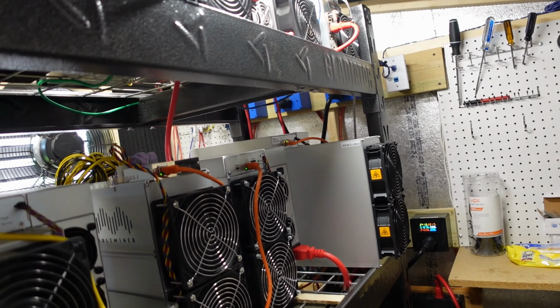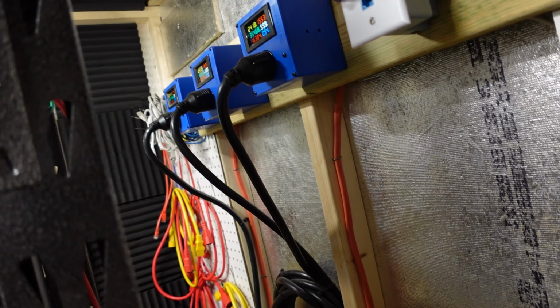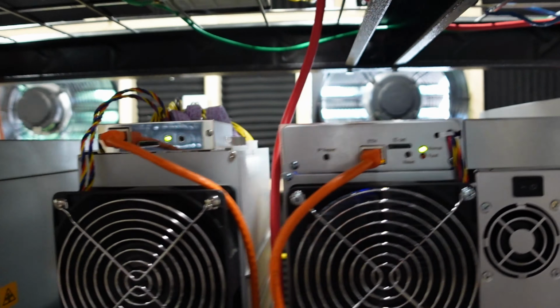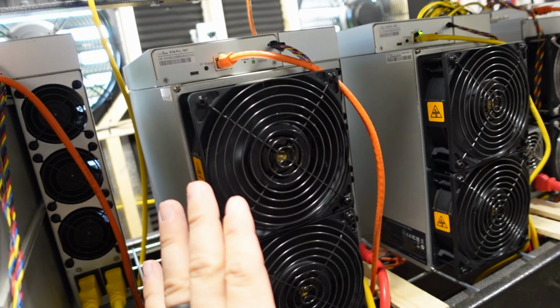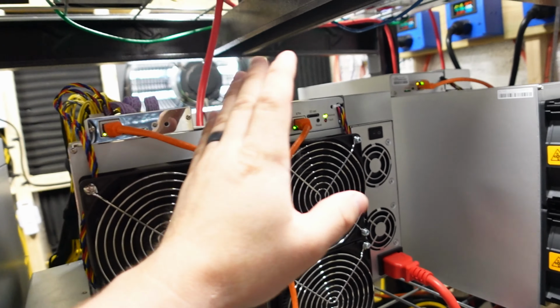So one of the things I said I do, I check power, check all my meters, make sure we're not going over in any way, shape, or form, staying safe with our electrics of our 80/20. Another thing we're doing is checking on any of our breakout boards. Make sure we don't have any 6 pins that are melting or anything dangerous going on. Then finally, we're just checking each piece of equipment to make sure that they're on, fans are spinning, no fault lights, no weird sounds.